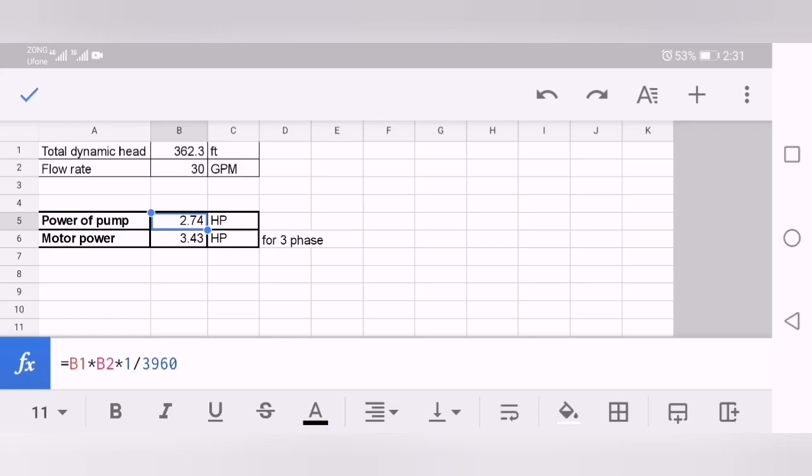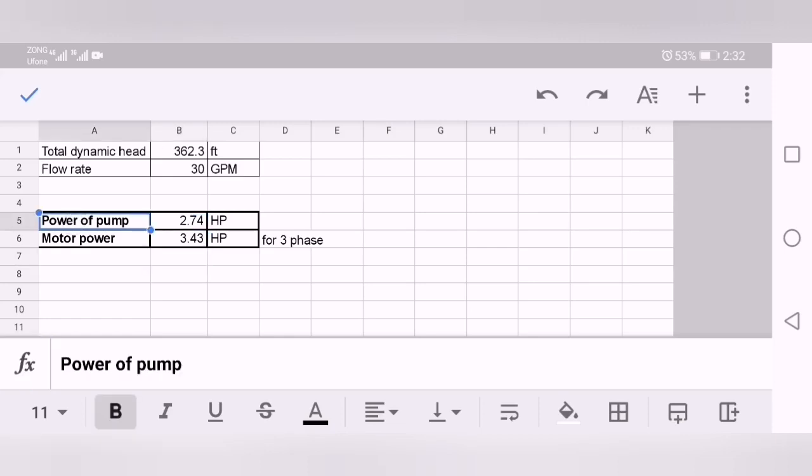One is your specific gravity. If you are dealing with water it's one. If you are dealing with oil, it may depend on its properties. It may be petrol or any fluid. Here just put the specific gravity and divide by 3960, and you will get the power of pump. This is the mechanical power of pump.